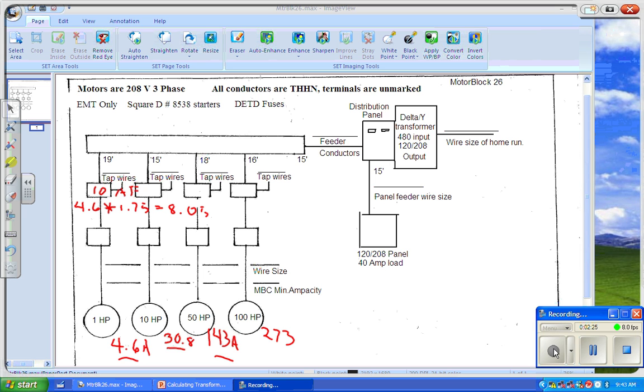Now let's look at 2, branch circuit overcurrent protection device. Conductors shall be permitted to be protected by the motor branch circuit, short circuit, and ground fault protection device, and shall require only short circuit and ground fault protection where the conductors do not extend beyond the motor control equipment enclosure. The rating of protection devices shall not exceed the value specified in column B. So column B is for when the conductors stay inside the control equipment. In other words, if your push buttons are in the front of the starter.